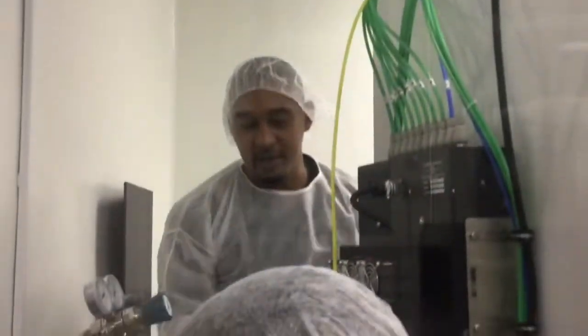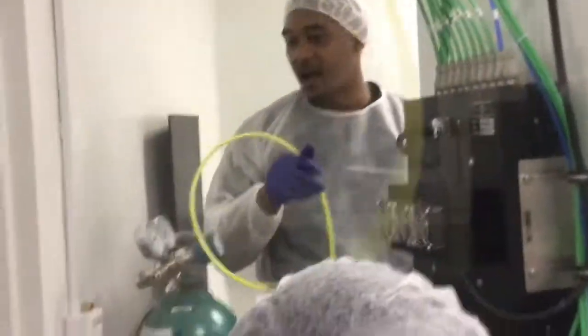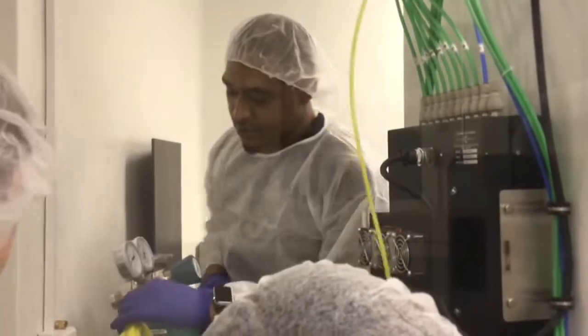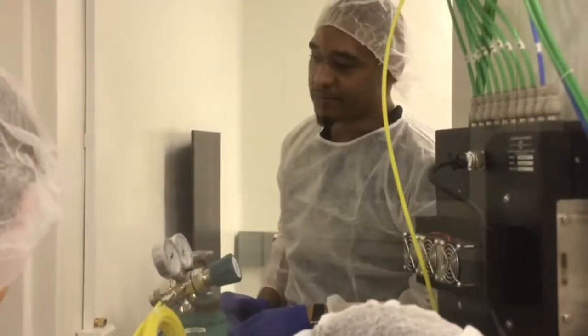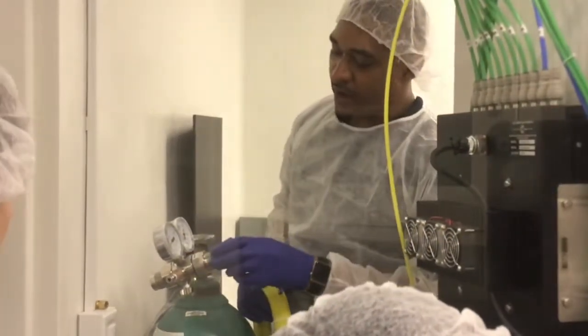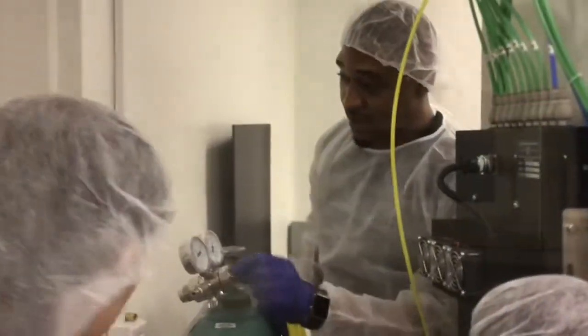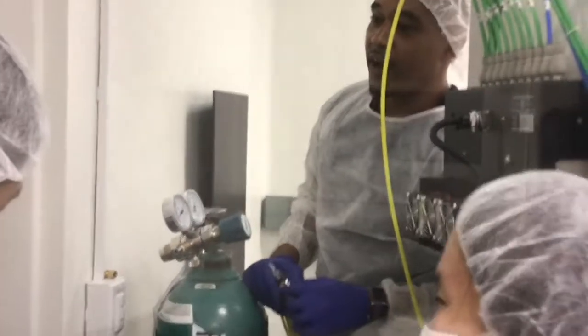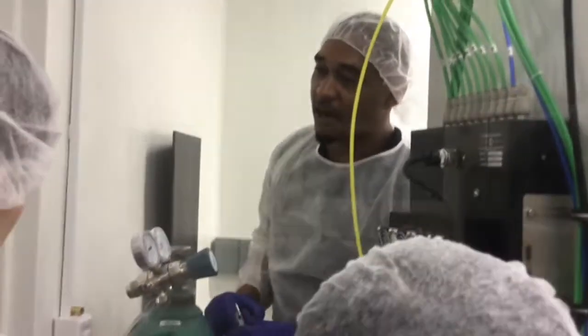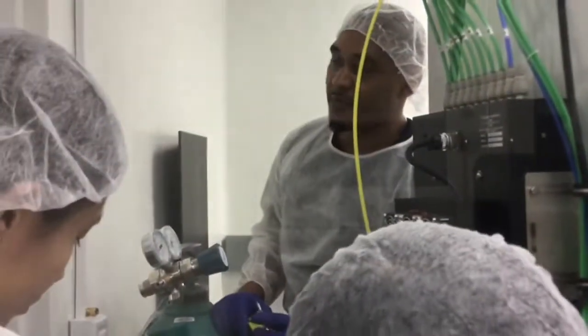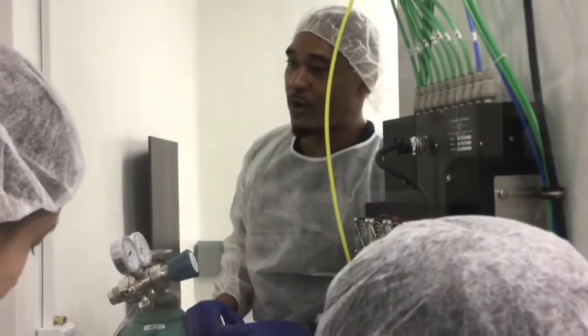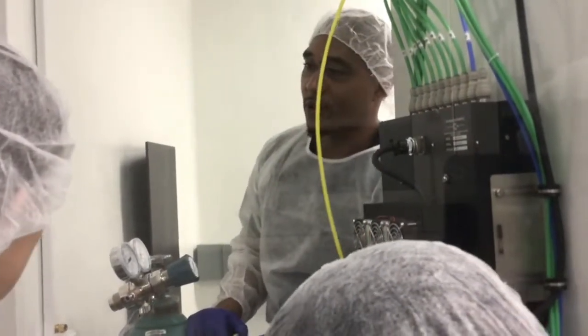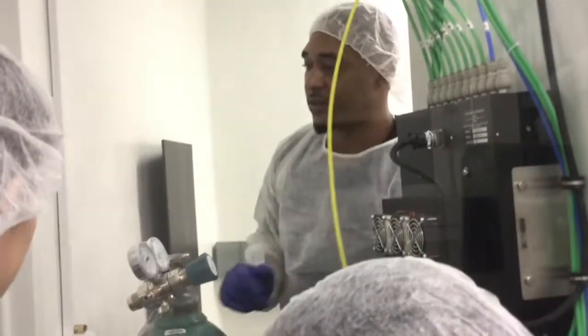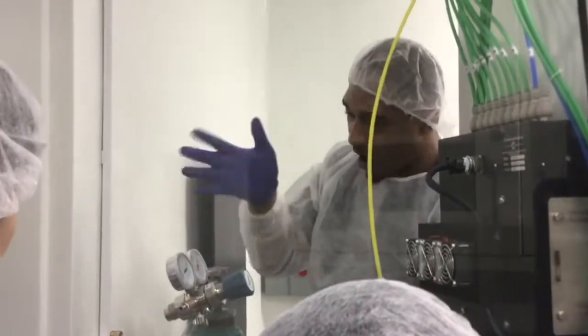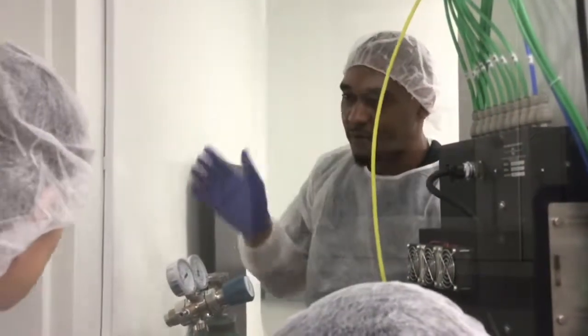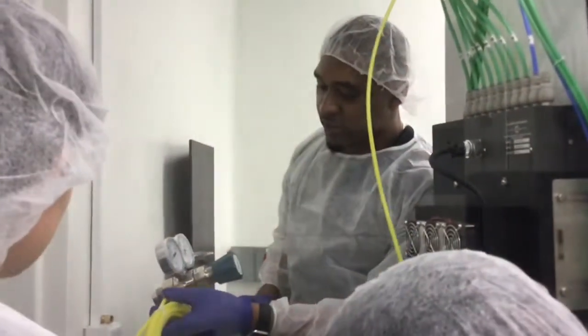Questions? We good? This line here is a calibration gas line. When you want to calibrate, you just plug in. When you're done calibrating, you just unplug. Usually I want this set around 10 psi. Write it down, 10 psi, it's important. If you go less than 10 psi, calibration might fail. If you go a lot higher than 10 psi, calibration might fail. 7 psi will work, 13 psi will work, 5 psi won't, and at 25 psi you are pressurizing the gas condition. So around 10 psi, about 7, 8, 9, 10, 11, 12, give or take.